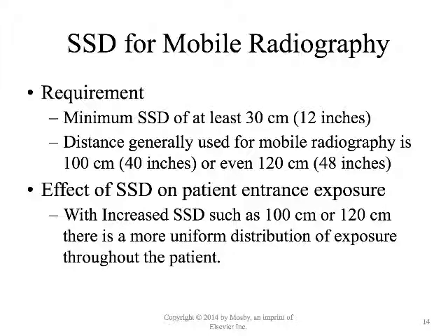You should not be able to get closer than 12 inches. In fact, most of our collimators and tubes are constructed in a way such to prevent that. So if you were to pull out the tape on the source to the SID measurer, it begins around 12 inches. Why? Well, it's a requirement.